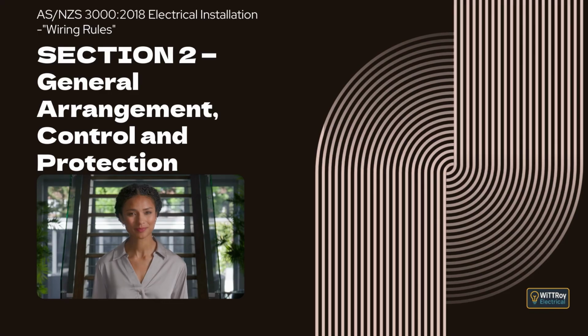Separation is required between the busbars in the functional units, between different functional units, between terminals used for external conductors, and between the general supply section and any safety service section of the switchboard. The purpose of this separation is simple. It prevents tools, loose parts, or accidental contact from causing an arc. It also helps ensure that one fault does not spread into another part of the switchboard.